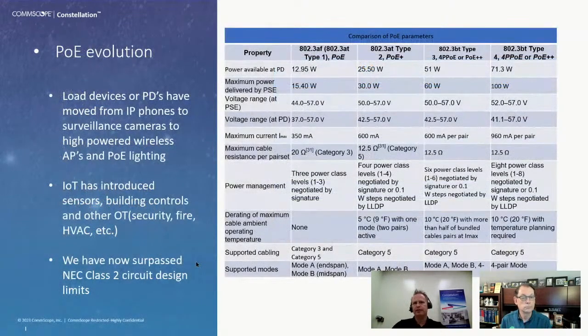I'm not going to cover all the data here, but for PoE, the important thing is the top two lines: power available at the PD and power delivered. As we've moved from the early 2000s with 15-watt IP phones to 30 watts, the standards moved too—60, 90 watts is the most current. That's really the limit in terms of Class 2 circuits.